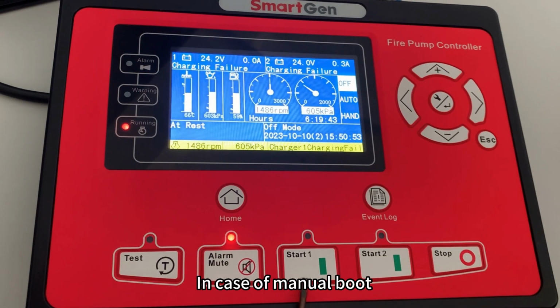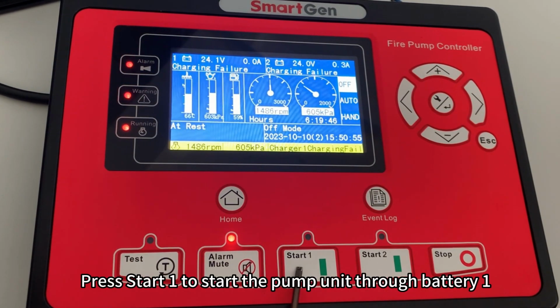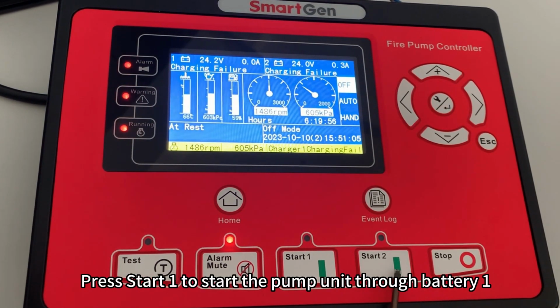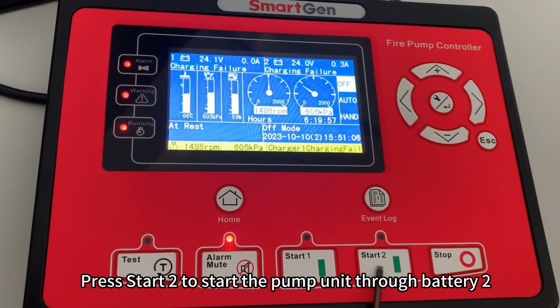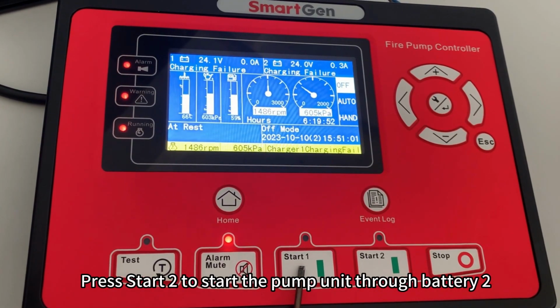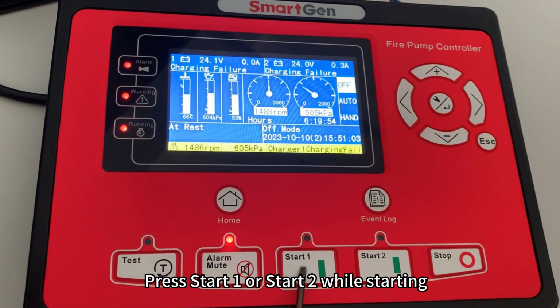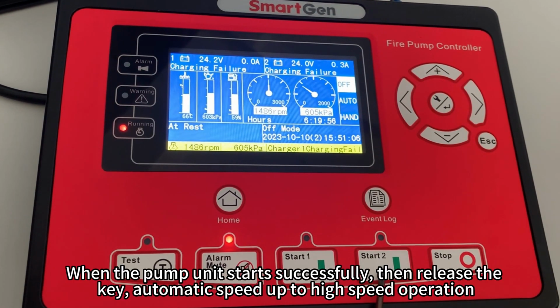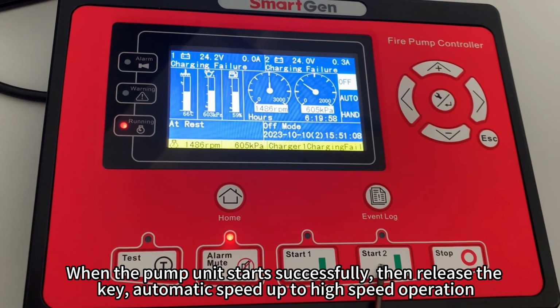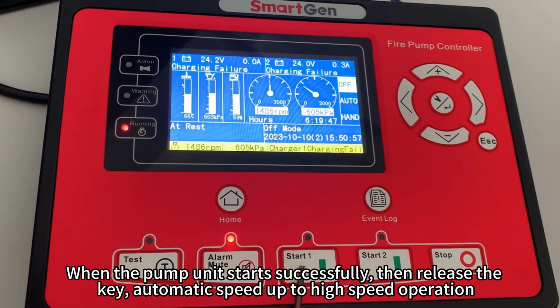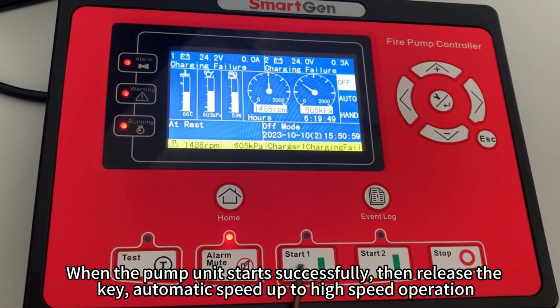In case of manual start, press start 1 to start the pump unit through battery 1. Press start 2 to start the pump unit through battery 2. Keep pressing start 1 or start 2 while starting. When the pump unit starts successfully, release the key. It automatically speeds up to high-speed operation.